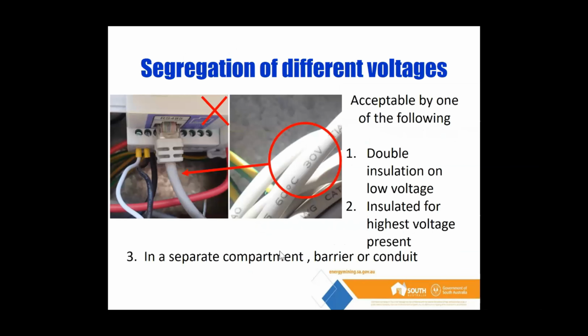Right here we have just a couple of photos of a battery solar setup again. However, you could probably take this into account for a number of other things. It could be a gate controller, it could be an air conditioning interconnector. At the end of the day, there's an industry term for this type of cable, and everyone calls it data cable. Now AS/NZS 3000 doesn't really talk about data cable. It talks about communications cable, and it talks about different cables of different voltages, but not data. Now it's not a communications cable because it's not connected to the telecommunications network. So the way we see it is it's a cable of a different voltage type.